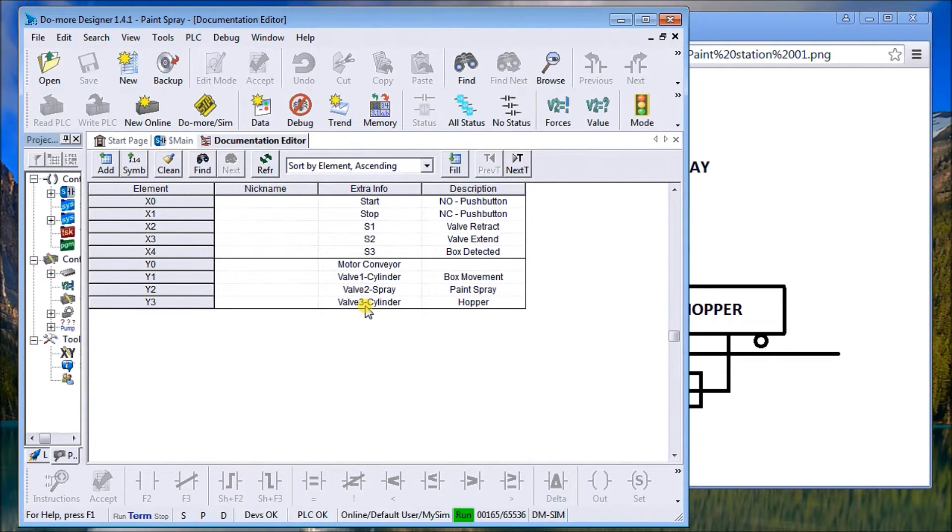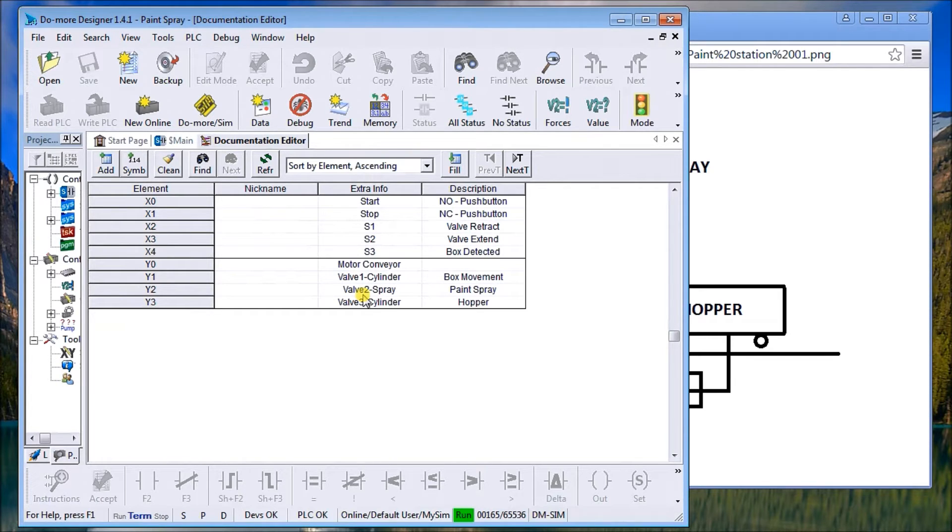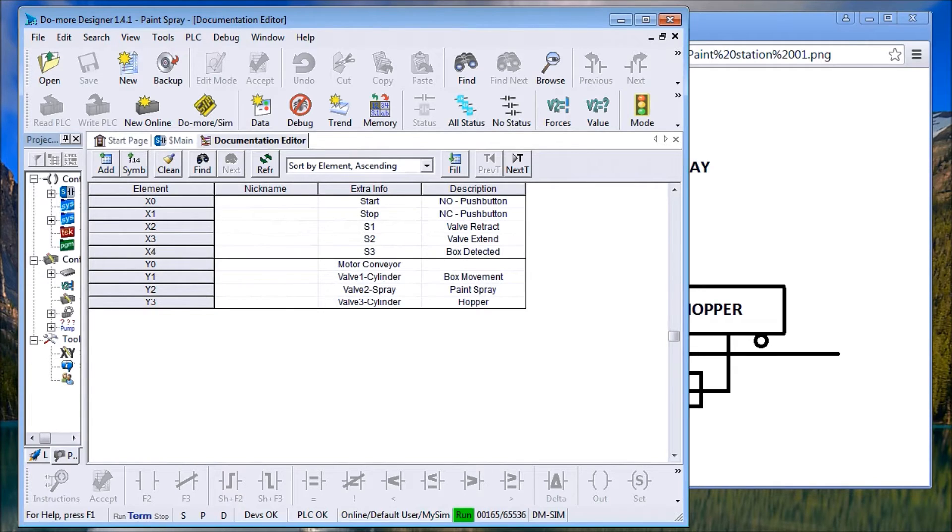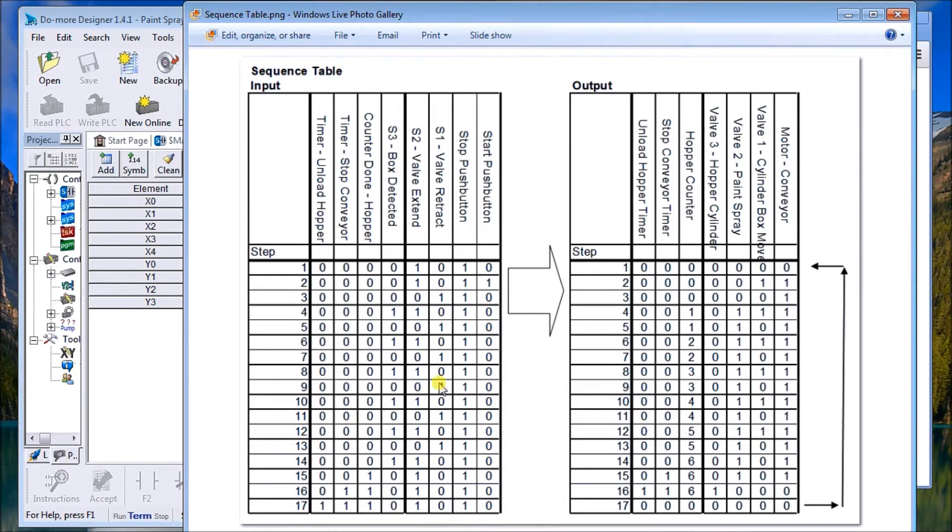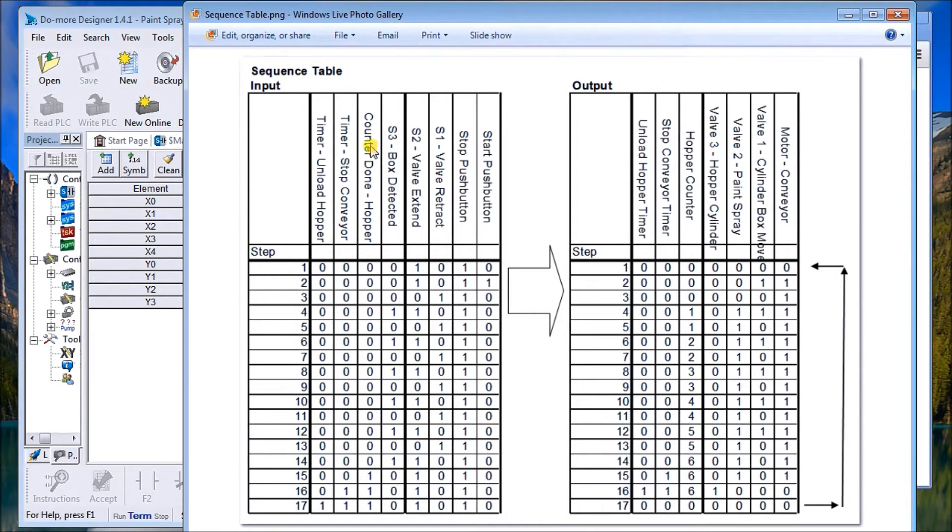Once I have that, then I want to develop the logical sequence of operation. Usually I do this by using a sequence table. If we call up our sequence table, it looks something like this. What I've done is besides my regular inputs being sensor three, I've also know that I need a counter because I'm going to count so many boxes going into the hopper before we move it, and we're going to have a timer to stop the conveyor at the last box so it will continue to load the hopper.